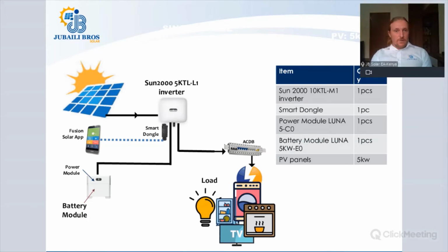Now, this is an off-grid scenario. Basically, it's the same as before, but it is off-grid. And this can work fine. Single phase, this will be a beautiful solution for a single phase off-grid scenario. This is a 5 kilowatt inverter, 5 kilowatts or 6 kilowatts of panels. You have 5 kilowatt hours of storage. You don't need a smart power sensor because there's no grid. The dongle is included in the box with the inverter. So all you really need is the power module, the battery module, and the inverter. This is an off-grid single phase scenario.